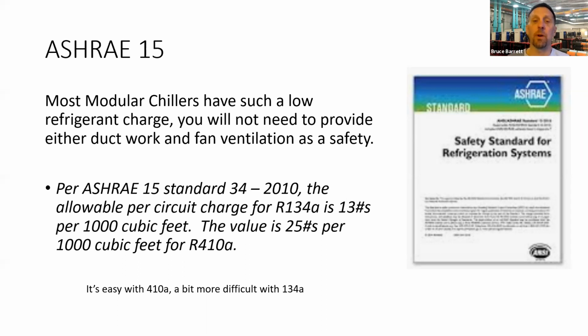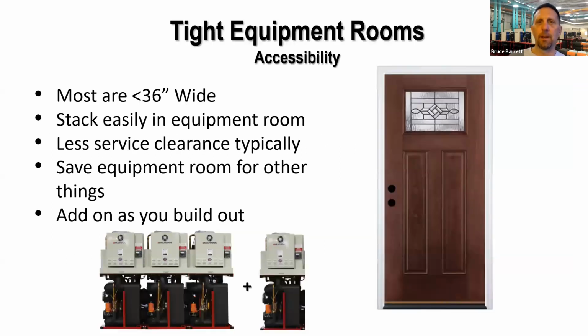So there you probably got to do a little more precise math to figure that out. But I've run into that as well, where we've got a series of modular chillers with all the same amount of charge, and they've also been under that requirement. So if you're doing a retrofit, that could be a big deal. The equipment room may not have it because it was well before that standard. You might be able to save a lot of money using a modular chiller, even though it has 134A. Tight equipment rooms, accessibility.